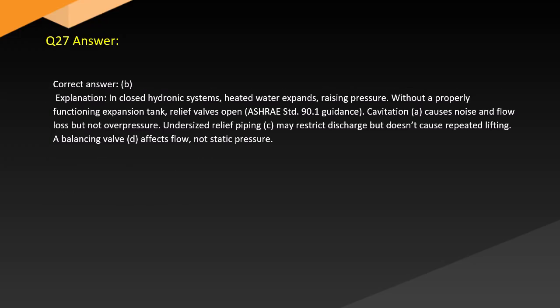Answer. Correct answer: B. Explanation: In enclosed hydronic systems, heated water expands, raising pressure without a properly functioning expansion tank. Relief valves open. ASHRAE Standard 90.1 guidance. Cavitation may cause noise and flow loss, but not overpressure. Undersized relief piping, C, may restrict discharge, but doesn't cause repeated lifting. Balancing valve, D, affects flow, not static pressure.